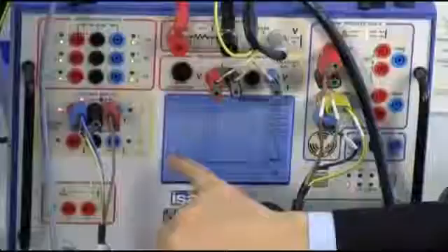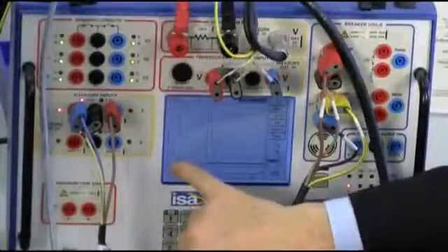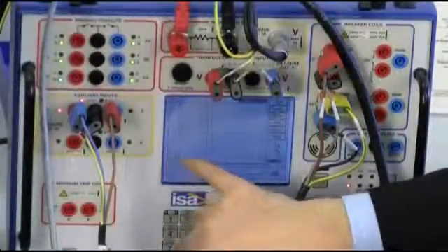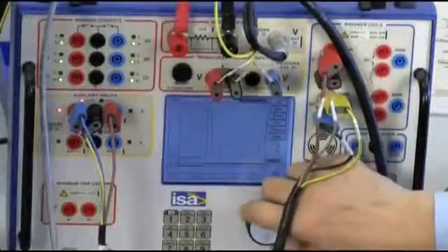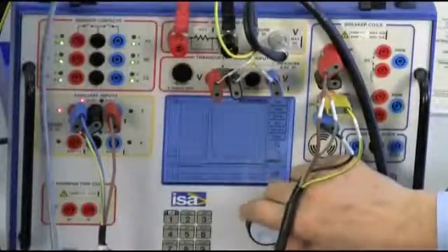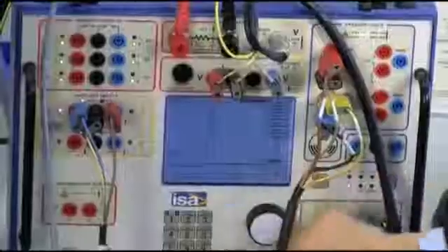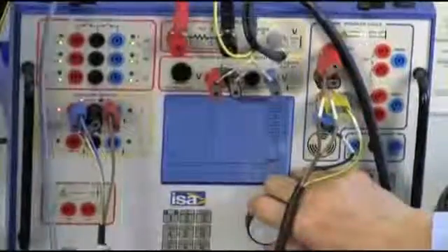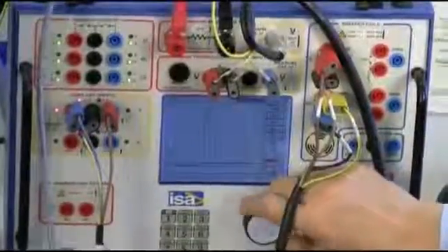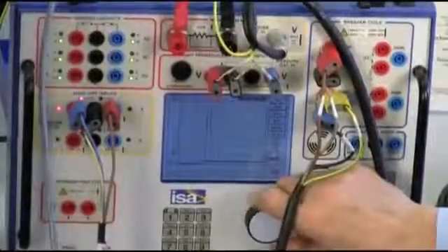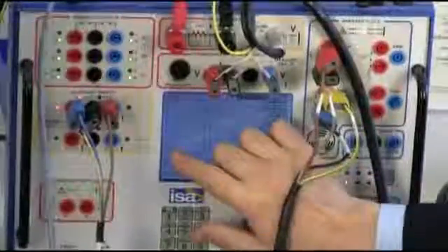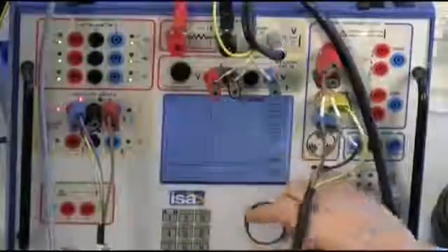Before my test, before the current actually started going through, there is no resistance measurement. Actually, it was open. Then there is this transient here. I move slowly. At the end of it, you may see that the resistance value is 0.697.